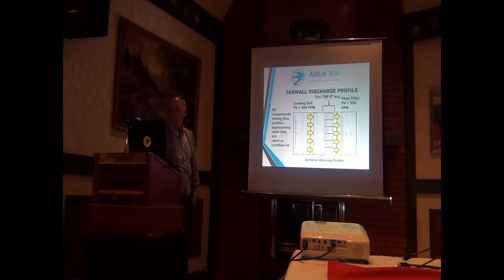Fan wall discharge profile. One word to best describe the profile on this is extremely uniform. Or I said one word, uniform. Bad one there. But why and how does it do that? You have similar to plenum fans here, but you have multiple smaller fans with smaller direct drive motors.